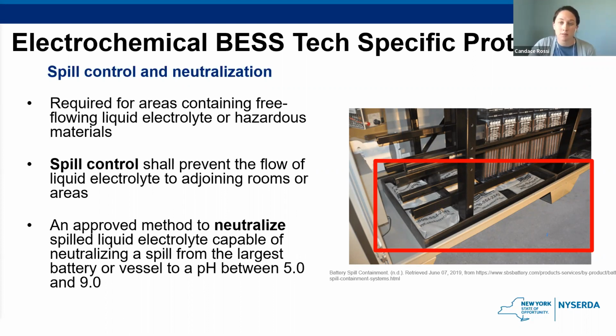So some of these systems can contain corrosives that can be well over 1,000 gallons, and these systems should have secondary containment, and in some cases might need that third level of containment. So lead acid is the major example here, as the battery has a liquid electrolyte, so they have a higher risk for spill control. And lithium ion batteries' electrolyte is not liquid, so this is not a safety requirement for them.